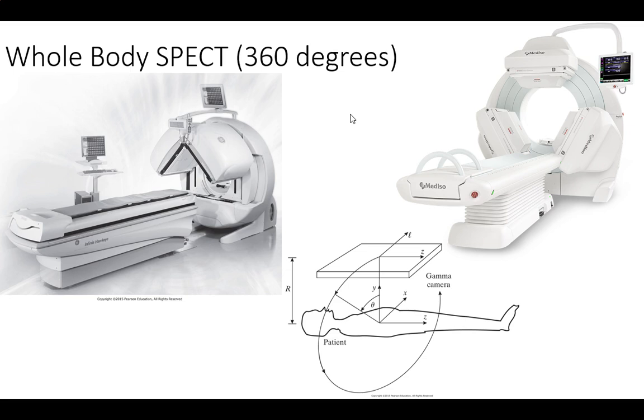That's all height adjustment to get in line. And then the bed will slide on a track here. You can see the track area. So that can slide in to get whatever part of the body is necessary inside. That's all remotely controlled from a booth so that you can slide the person in or out. They try to leave these areas open in between because people freaked out when they were closed in. If you see old models, they're closed in, but then it was this long, really thin tube, and the number of people who freaked out was very high.